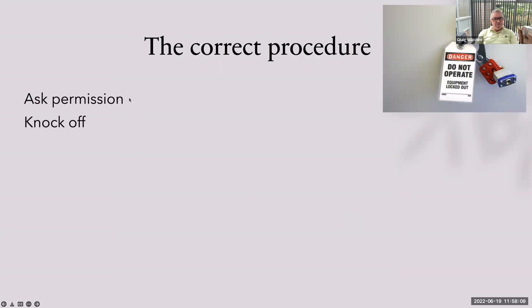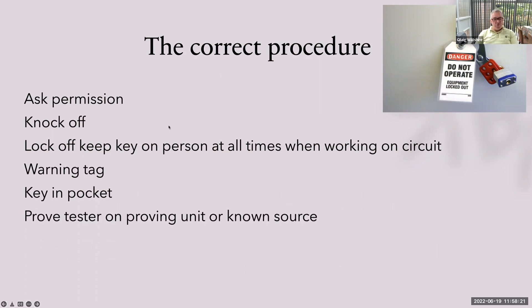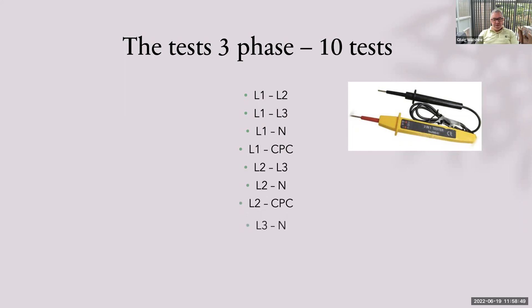The correct procedure is: ask permission, knock off, lock off, keep your key on your person at all times, warning tag, key in pocket. Prove the tester on a proving unit or known source that it's working. Test and reprove the tester. The tests at single phase are line to neutral, line to earth, neutral to earth. For three phase, the best way is to work each phase until it's complete: L1 to L2, L1 to L3, L1 to neutral, L1 to CPC, L2 to L3, L2 to neutral, L2 to CPC, L3 to neutral, L3 to CPC, and then neutral to CPC.